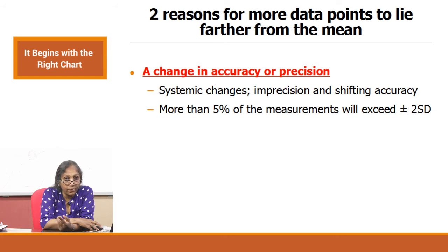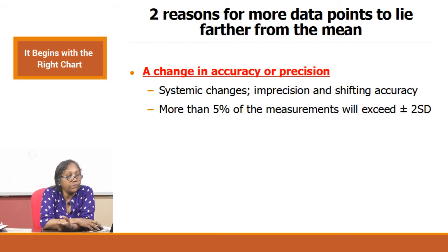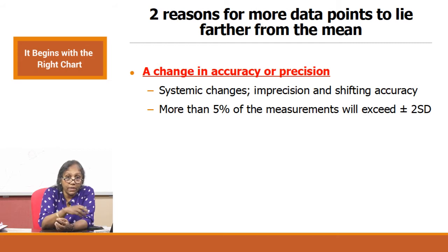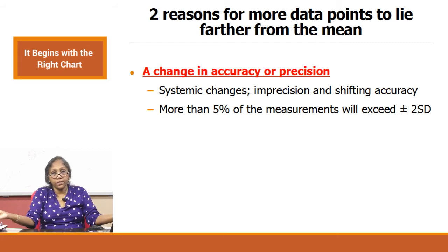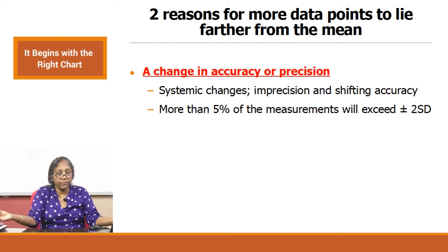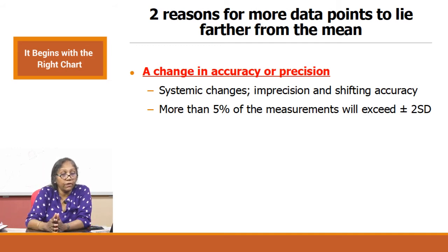To recap on the Gaussian: only 2.5 percent maximum points are allowed on each side of the Gaussian curve — 2.5 percent beyond your 2 SD limit on the plus side, 2.5 percent beyond your 2 SD limit on the negative side. Together, 5 percent outside plus or minus 2 SD is all that is allowed.